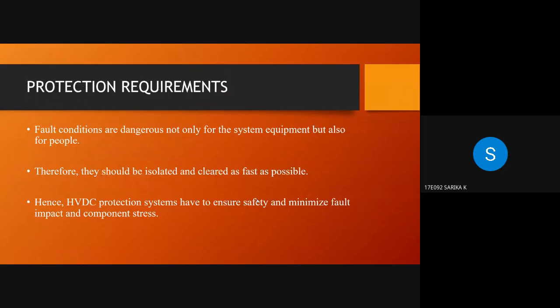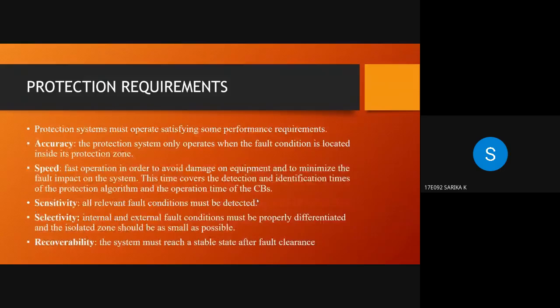Protection requirements needed for these challenges. Fault conditions are dangerous not only for the system equipment but also for people. Therefore, they should be isolated and cleared as fast as possible. Hence, HVDC protection systems have to ensure safety and minimize fault impact and component stress. Protection systems must operate satisfying some performance requirements. The requirements are accuracy, speed, sensitivity, selectivity, recoverability.